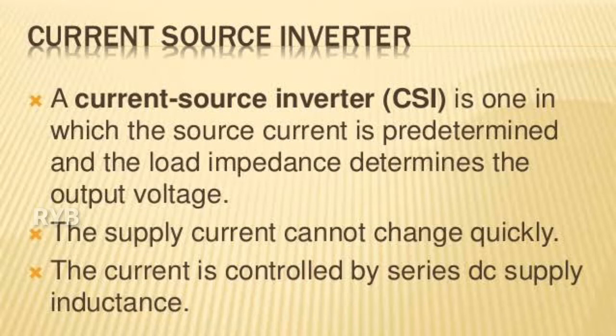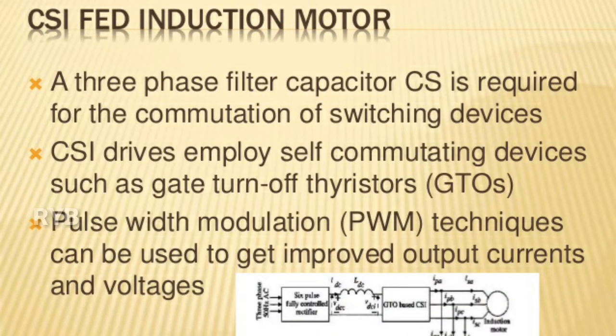A voltage source inverter (VSI) is fed by a stiff DC voltage, whereas a current source inverter (CSI) is fed by a stiff current source. A voltage source can be converted to a current source by connecting a series inductance and then varying the voltage to obtain the desired current. A VSI can also be operated in current control mode, and similarly a CSI can also be operated in voltage control mode. Inverters are used in variable frequency AC motor drives, UPS, induction heating, and static VAR compensators.